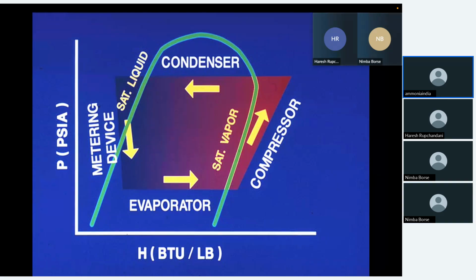As you see, the evaporator inlet... but in ammonia plants we normally use an accumulator, and we separate out that gas formed during expansion and allow 100% liquid to come into the flooded chillers. Therefore, ammonia plants are always more efficient as compared to direct expansion HCFC plants. So this is an important point to remember. What is the difference between a DX plant and a flooded plant? 99% of ammonia plants are either flooded plants or pump circulation systems in which 100% liquid enters the evaporator.